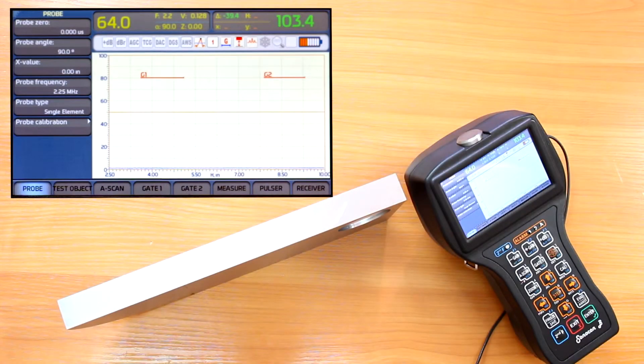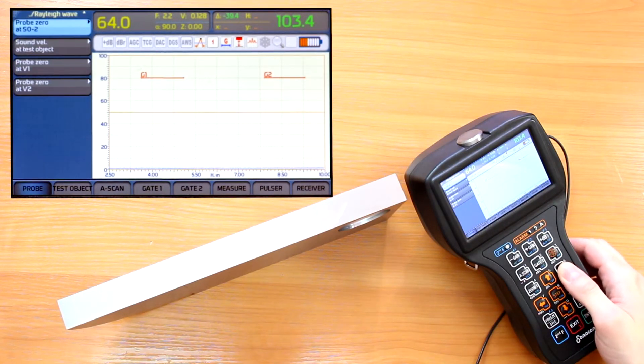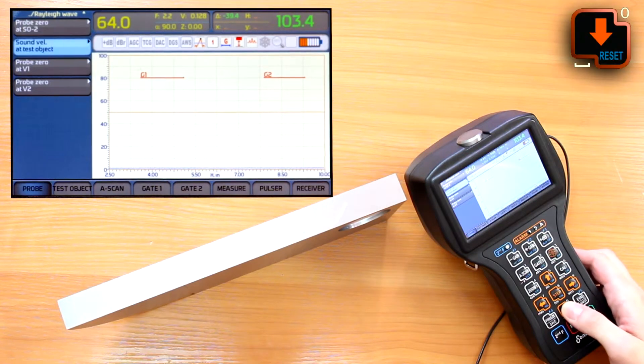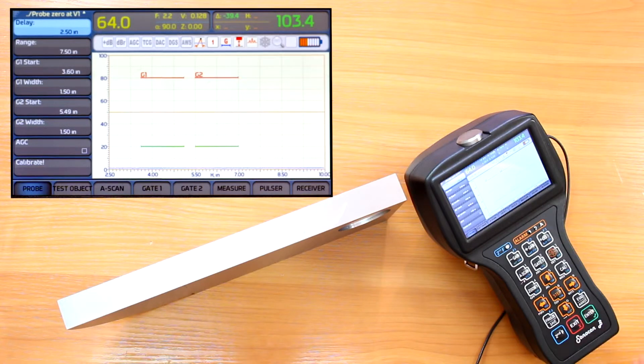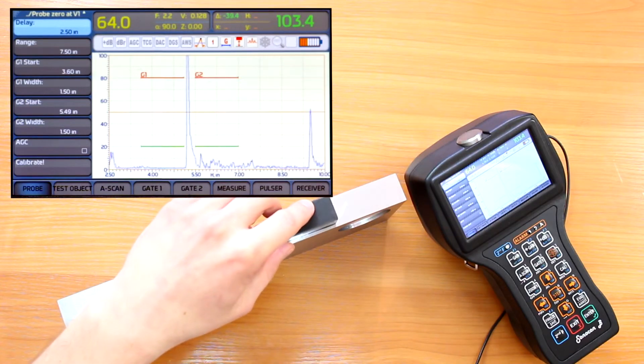The last probe type I'll show the calibration procedure for is the surface or Rayleigh wave probe. I'll use the V1 standard for probe zero and sound velocity calibration. To start the calibration I press the calibration button and choose and activate the 'Probe zero at V1' item.